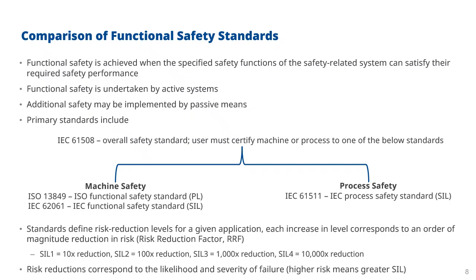So the standards generally define a risk reduction level for a given application. And the idea is that each increase in level, so for example, if you go from PLD to PLE, or if you go from SIL 2 to SIL 3, each increase in level corresponds to an order of magnitude in risk reduction factor, or RRF. Now, some of the calculations for this get very, very complex. You need to look at things like probability of failure to danger. You need to look at the amount of failures that can actually be detected. You need to look at if there's failures which can affect the system leading to harmful impacts or failures which don't lead to harmful impacts. And there are a lot of calculations involved here.